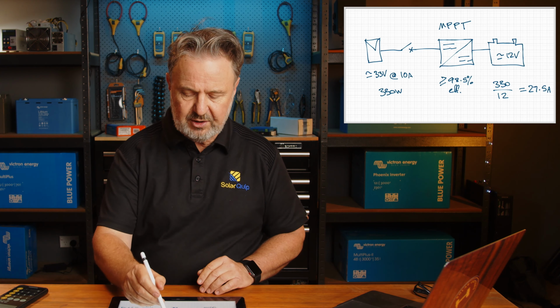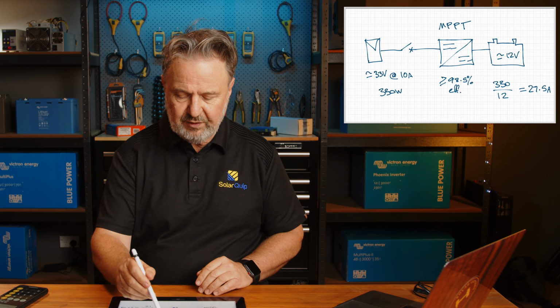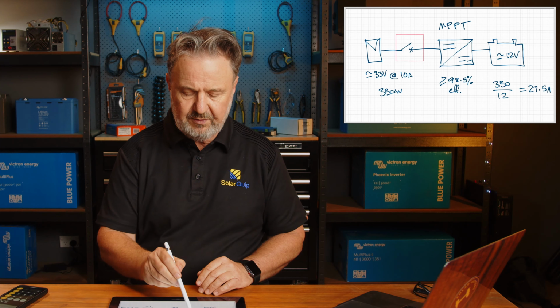The other thing I'm considering, and this is a safety feature, is that we have a device here for overcurrent protection. Now I've only shown a single line diagram here - it depends on whether this is an earthed array. That means functionally earthed, where one of the two poles, positive or negative, is connected to earth. But it's most common to have what's called a floating array.